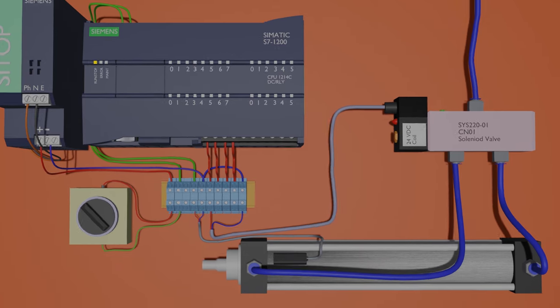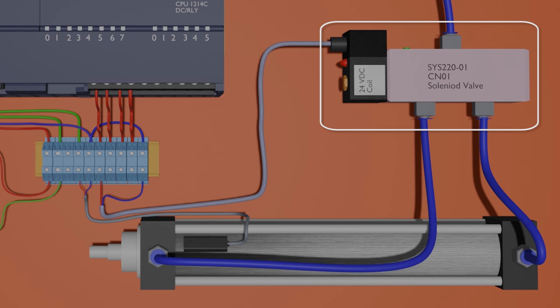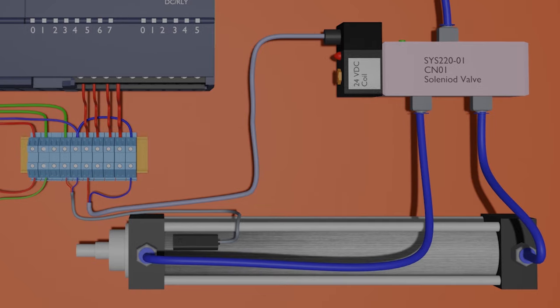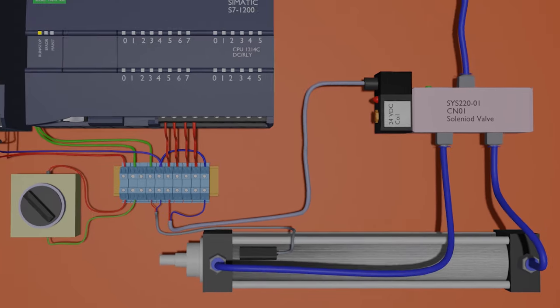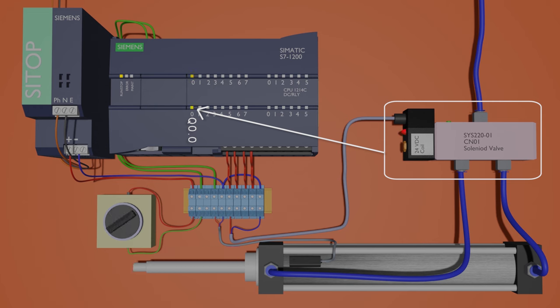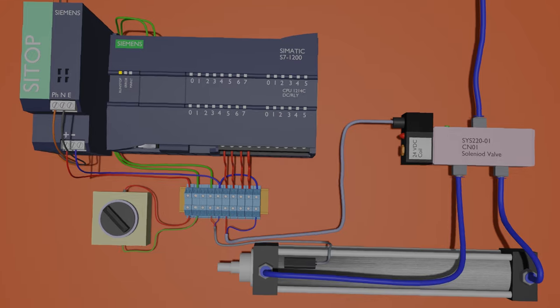Next, we have a pneumatic solenoid valve to supply compressed air to the cylinder. This solenoid has a coil which operates at 24 volt DC. This coil is connected at Q0.0 output terminal of the PLC. So when this output Q0.0 is turned on, this coil gets energized and it supplies the compressed air to the cylinder, and the cylinder shaft actuates a linear motion.